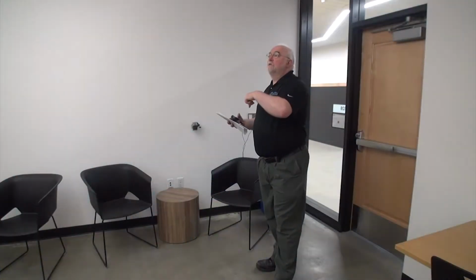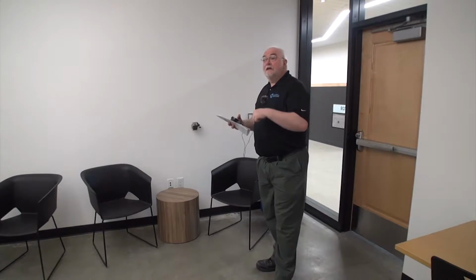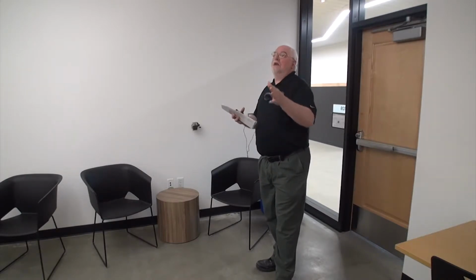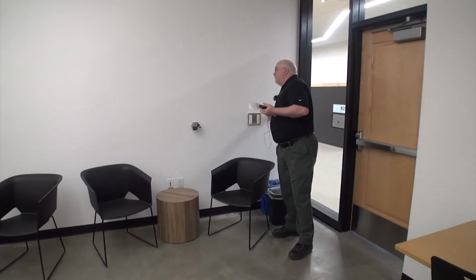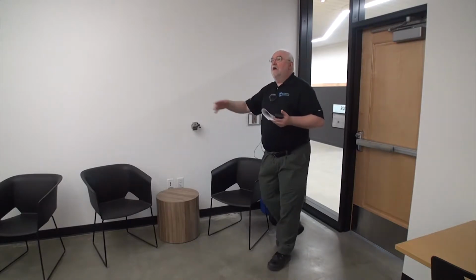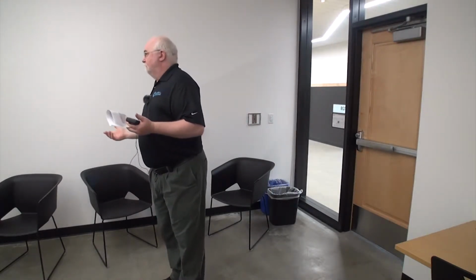Can we go through here? The reason I brought you guys in here is this room is set up as an office space versus a classroom space, meaning there's just one switch that controls the whole area. As you saw when I walked in, nothing happened. I had to turn the lights on. It's in vacancy mode, with a 15-minute timeout.